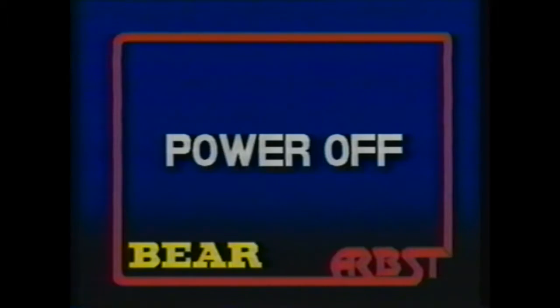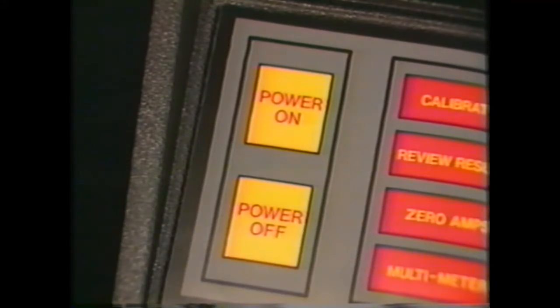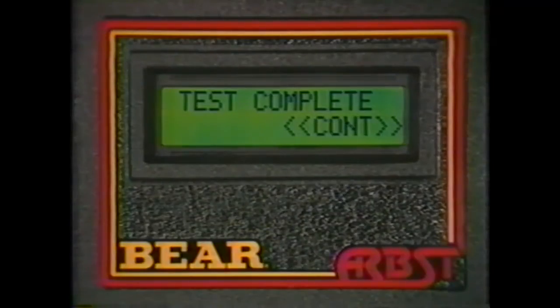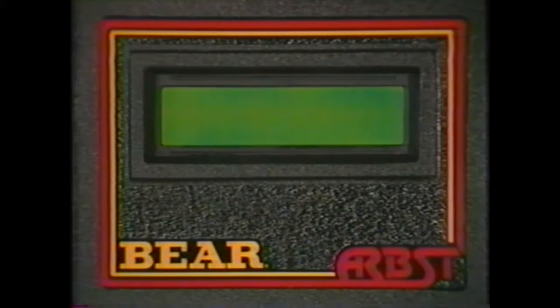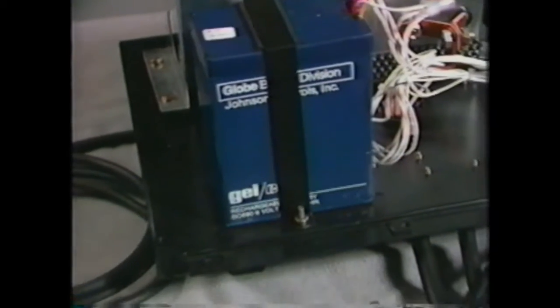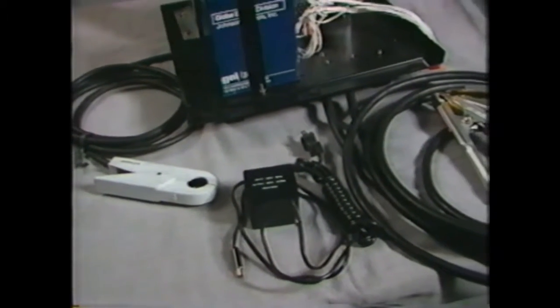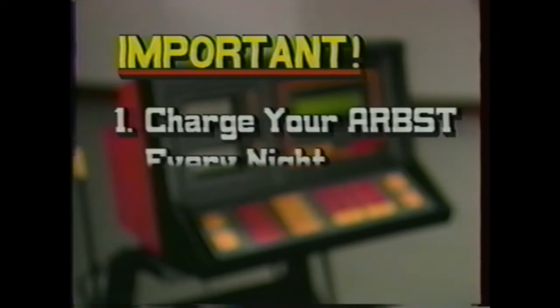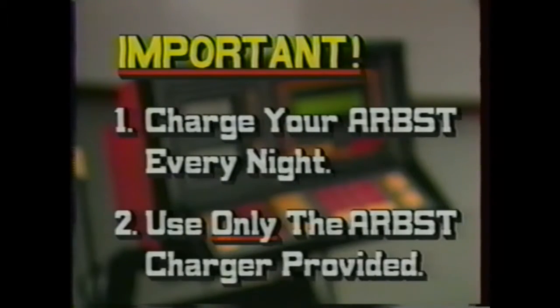Finally, when you're all through testing, press the Power Off key to shut the tester off. If you forget to do this, the tester will automatically shut itself off if it is not used for 15 minutes. Your tester comes with its own internal 6-volt battery and charger. The battery must be charged overnight at least once a week. It will not hurt the battery to charge it every night, so we recommend you get in the habit of putting the tester on the charger every night. Use only the charger provided with your tester. There are other chargers that look the same but may damage the tester.